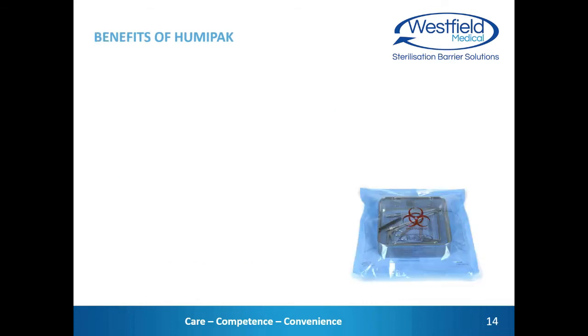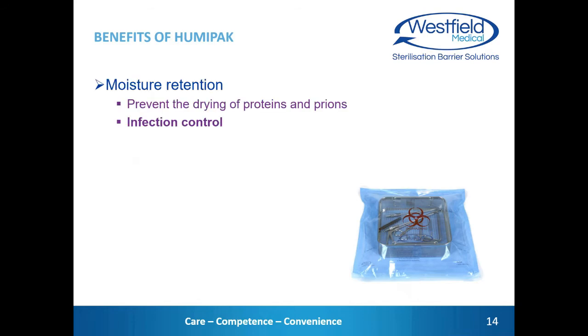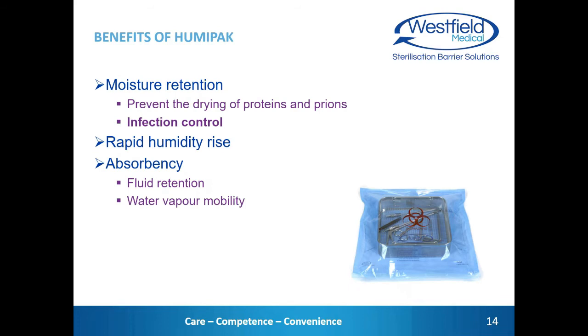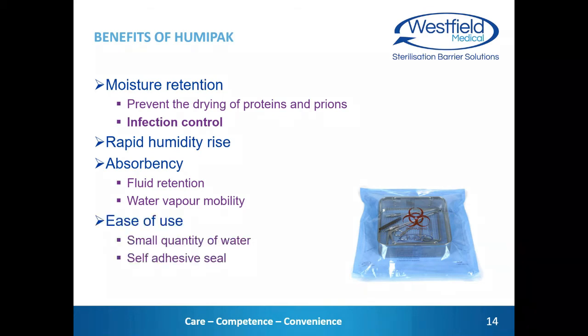So a quick look again and recap on some of the benefits. The primary function is to prevent drying and in some areas compliance with guidelines. The specific design of HUMIPAK creates a fast humidity rise, so it starts working more quickly. The absorbency of the inner layer retains any fluids in the pack, but it also allows the water molecules to move easily into the air and become effective in keeping the contents moist. And it's easy to use, using water, not chemicals, avoiding potential compatibility issues with some instruments maybe, or possible fixative effects with some types of disinfectant. And it's an easy to form seal.